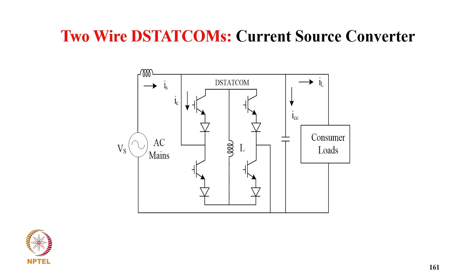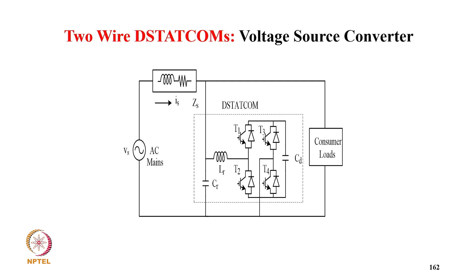Similarly, we have a 2-wire D-STATCOM with a voltage source converter. Here you can see we have a very less lossy DC link capacitor CD, and then we have a very small inductor as a filter, which can even be realized with the help of a transformer if required, and with CR it works as a ripple filter. With proper control, you can generate the compensating current with the help of this. What the load really needs locally can be supplied locally, so you don't have to burden the grid.